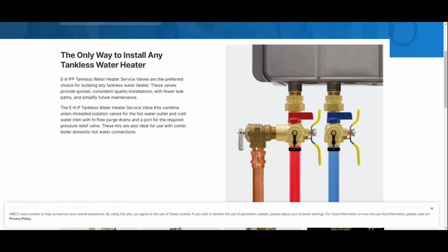Okay, so this is the bottom of the tankless water heater. So the point of these valve kits, and I see this all the time where a tankless has been installed. In Simcoe County, our water is very hard here. So if you're not running a softener, that's another issue. But even if you are running a softener, you need to yearly flush your tankless to avoid the heat exchanger from gumming up and wrecking it. And again, that's not covered under warranty if you're not doing your maintenance on that. They will straight up deny warranties for bad heat exchangers if there's no maintenance proof and the water is really hard going into it. So I'll explain a little bit about what this valve does.